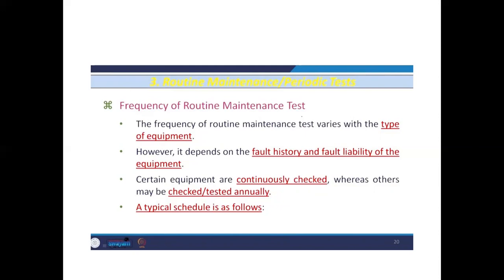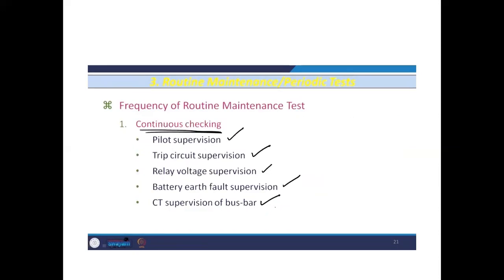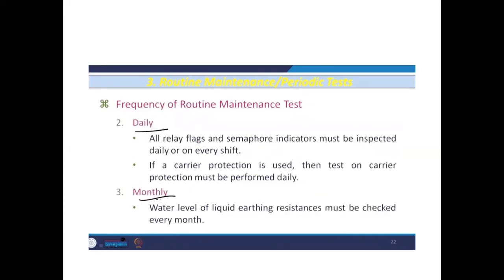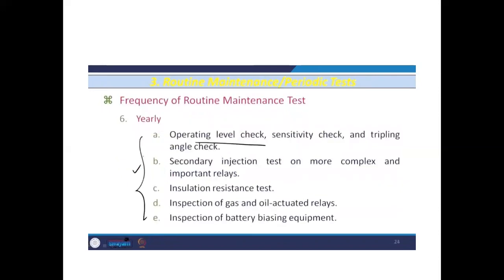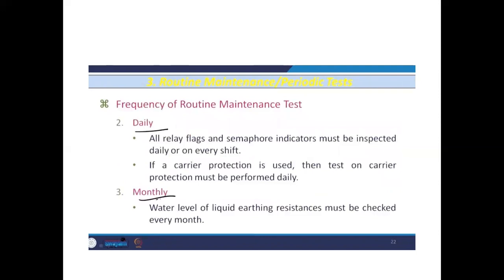A typical schedule is as follows. Continuous checking: the pilot supervision, the trip circuit supervision, the relay voltage supervision, battery earth fault supervision, and CT supervision of the bus bar. Okay, so these are the continuous checking. Now the frequency: some are daily, some are monthly, bi-monthly, half yearly, and yearly. Okay, so what are the daily ones?